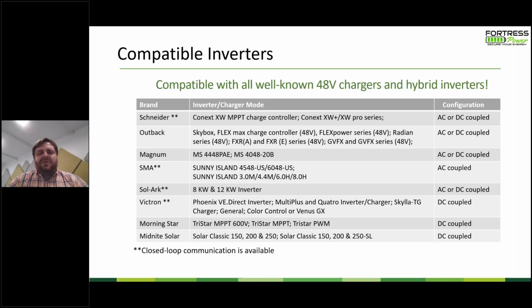and performance when the battery banks are well sized. The main technical advantage of closed loop is that it allows you to more safely operate an undersized battery bank. There is a limit to that. At the end of the day, you don't want to have an undersized battery bank, but sometimes you'll see some flexibility there, where if you have a closed loop inverter you can get away with using two E-Flex as the minimum. Whereas if you select the same size open loop inverter, you would have to do three E-Flex to meet the minimum sizing requirement.